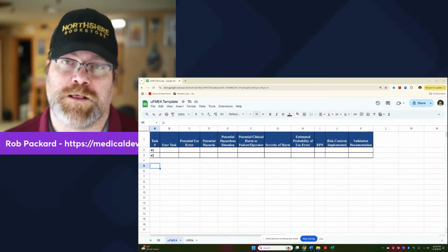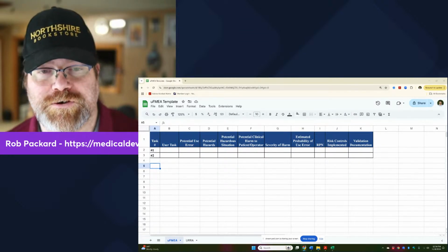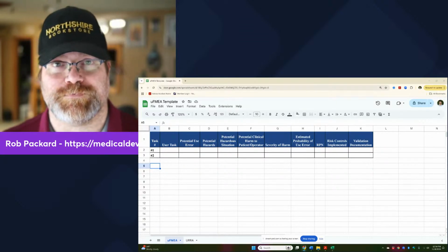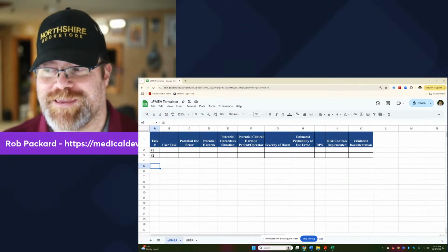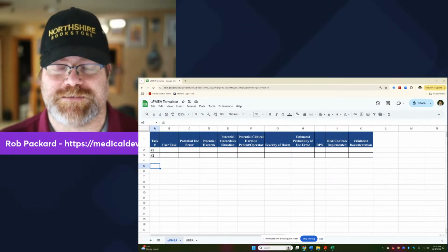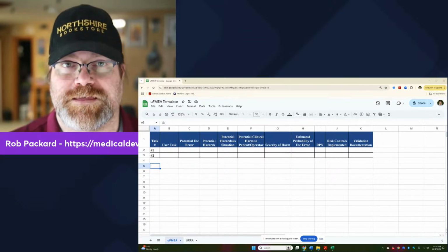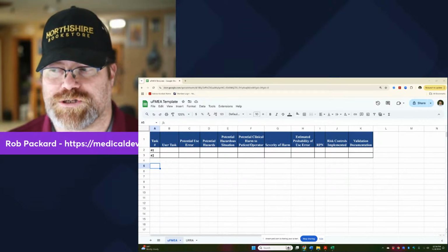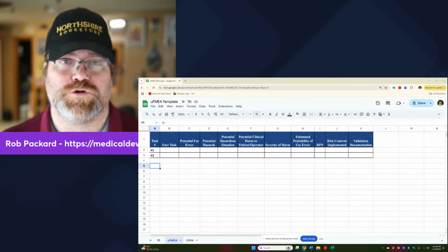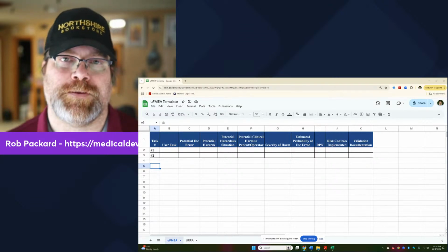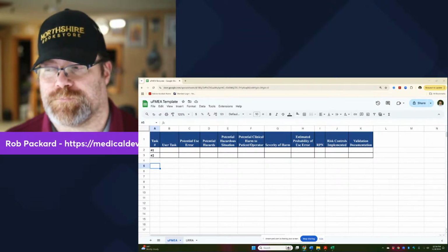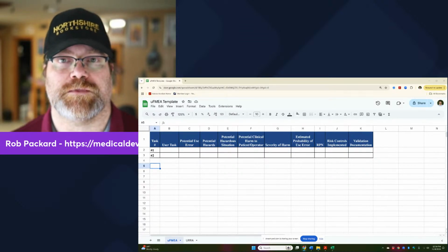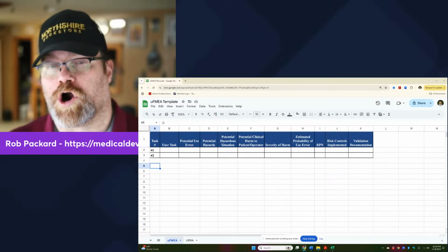The severity of harm. Well, if my fever is 99 or 100, probably it's just discomfort. But if my fever is 107, it could be a little bit more substantial. So it depends on what the severity of the temperature is, the severity of the misdiagnosis, the severity of the incorrect therapy that I'm going to provide to the patient. So depending on what the situation is, it could result in a different harm, and we generally try to pick the worst case scenario. You could write down both possible scenarios and track them both, but generally we focus on the worst case.